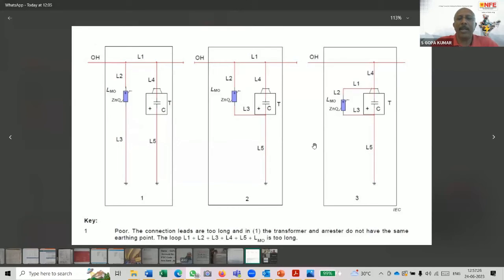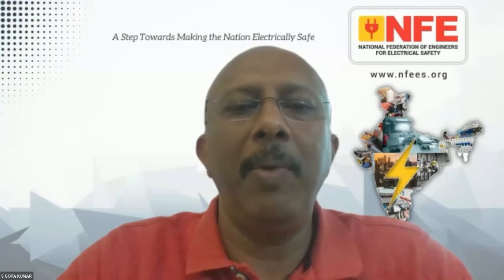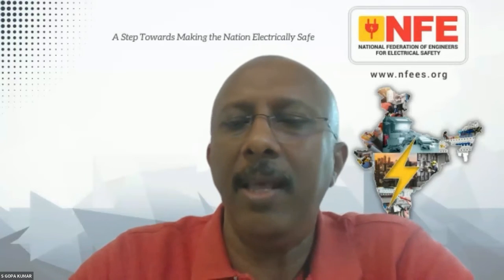In that case, you go for connection number 2 or 3. The surge arrestor lead earth wire has to be connected to the transformer tank itself. In connection number 2 or 3, you get the best possible protection by using the surge arrestor. Connection number 1 is okay for extra high voltage, but not for 11 kV, 22 kV or 33 kV distribution class. So I hope the answer is clear. Please refer to the standard. Very clear explanations are given.